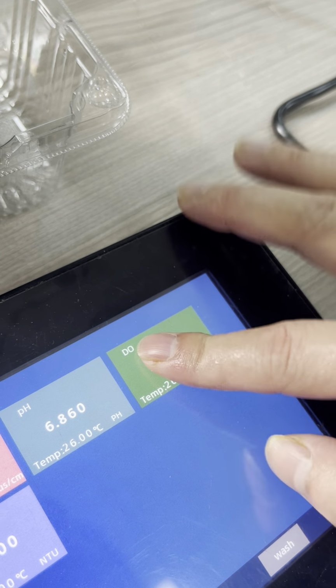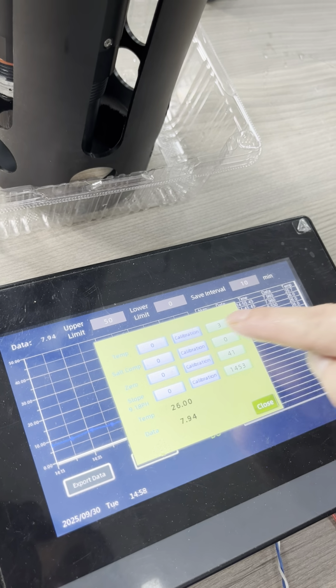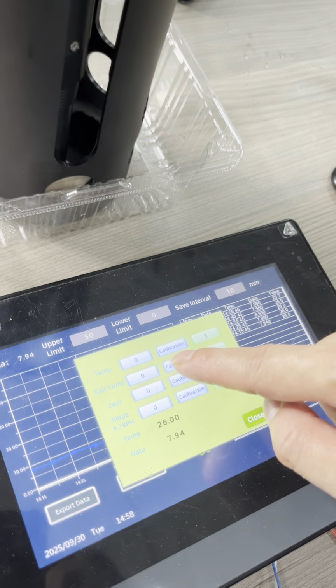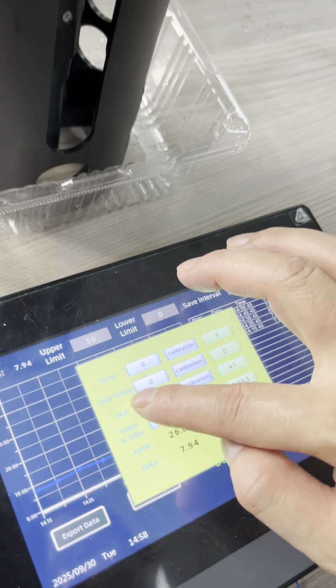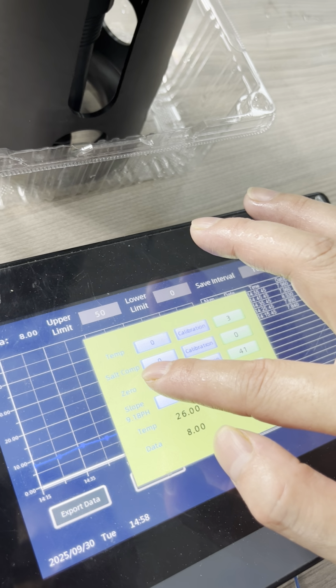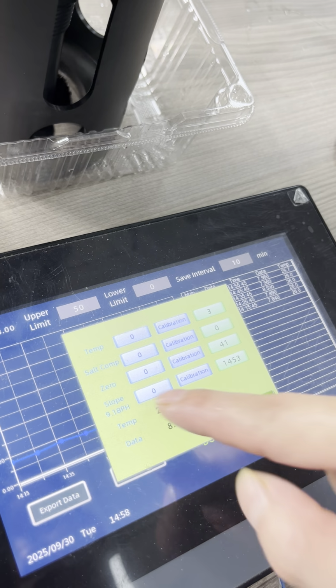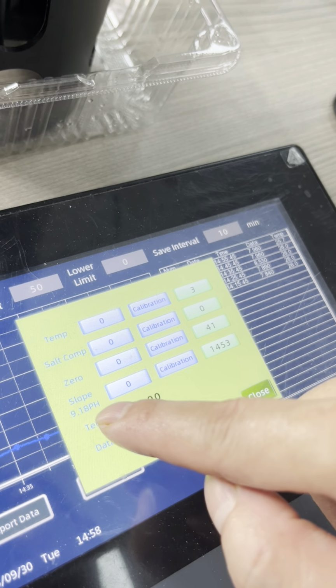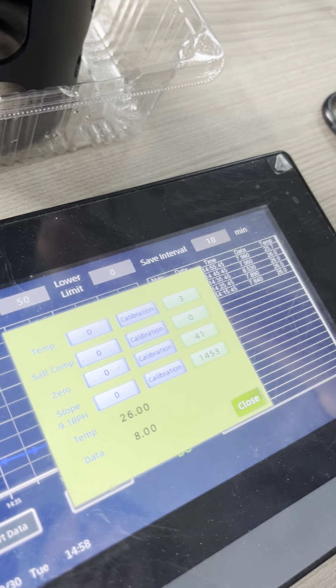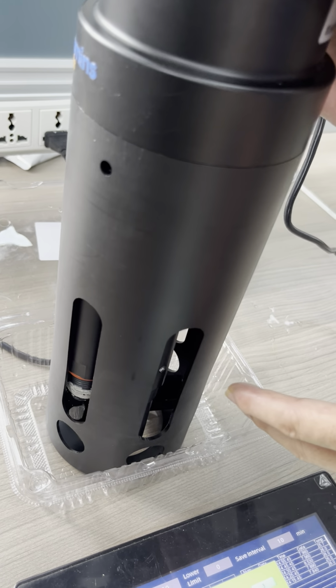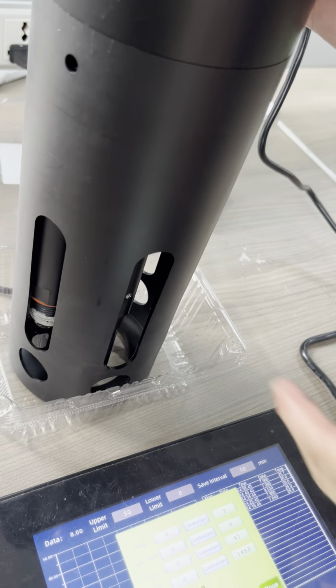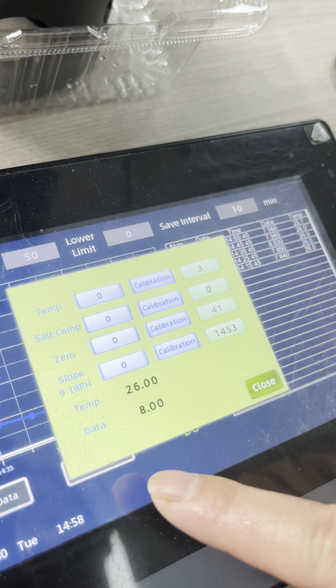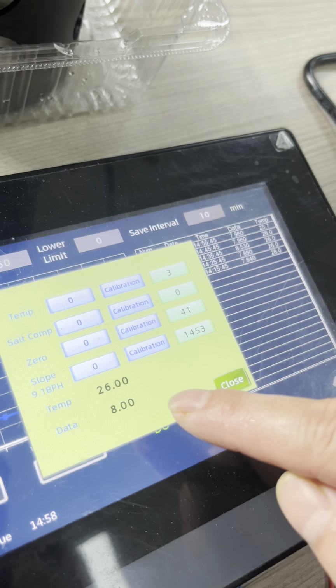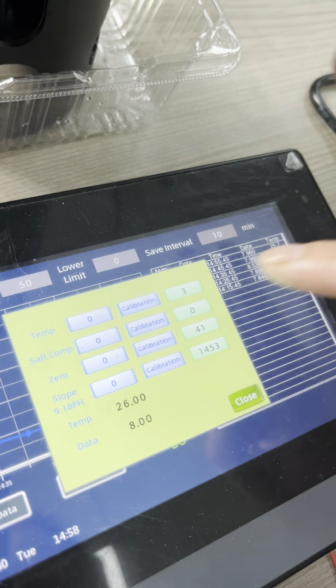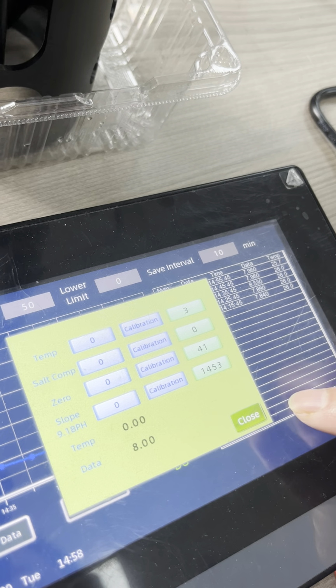Now we come back to do DO calibration. Click calibration. There's no need to do temperature calibration because we have done it. For the salt compensation, there's no need to do it. For the zero, there's no need to do it. We only need to do the slope calibration. We put the sensor into standard solution, air saturated water, and after 3 minutes, the data will be stable. Then you click calibration. Now the calibration for the oxygen sensor is done.